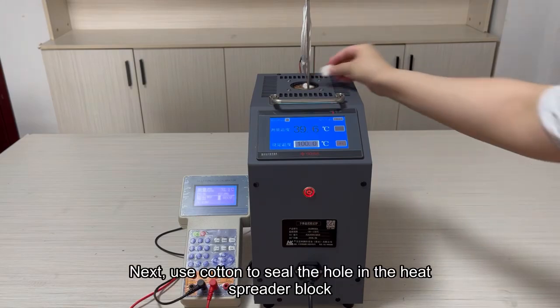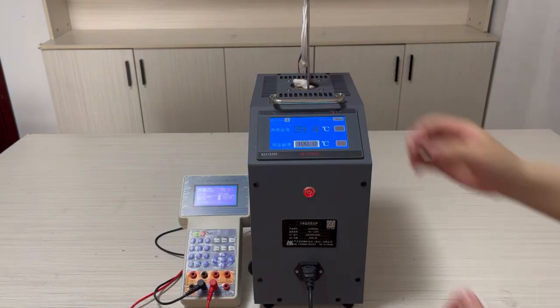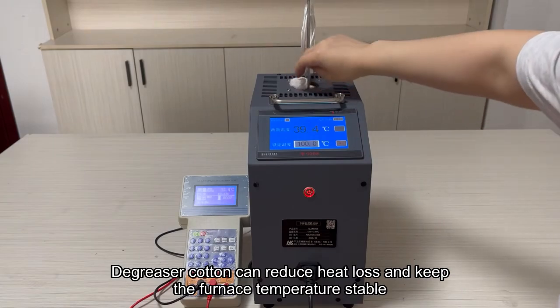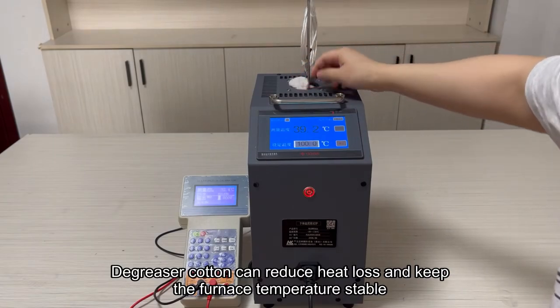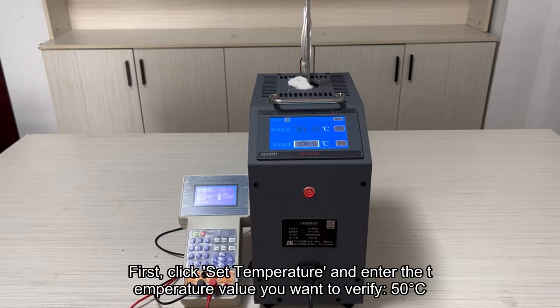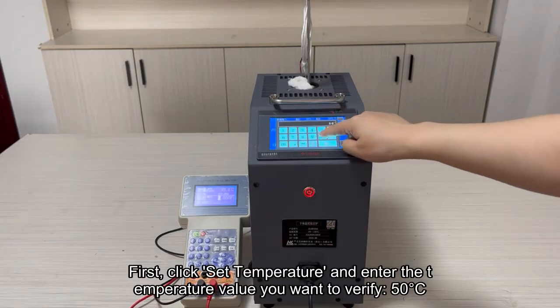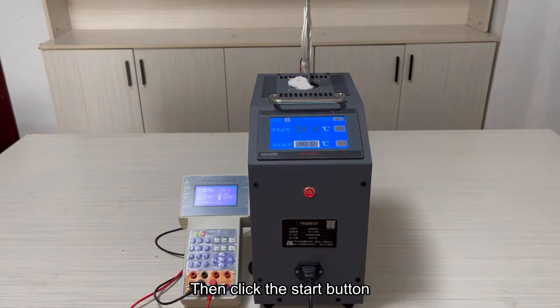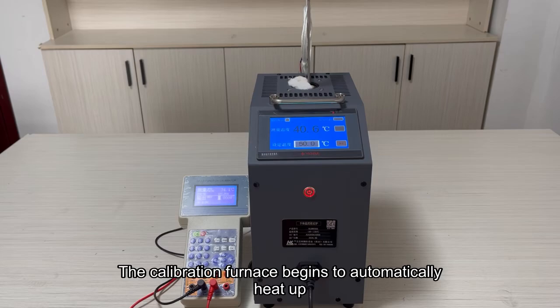Next, use cotton to seal the hole in the heat spreader block. Degreasing cotton can reduce heat loss and keep the furnace temperature stable. Next is the heating mode. First, click Set Temperature and enter the temperature value you want to verify, 50. Then click the Start button. The calibration furnace begins to automatically heat up.